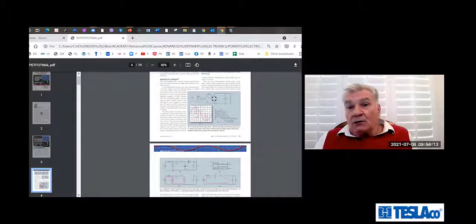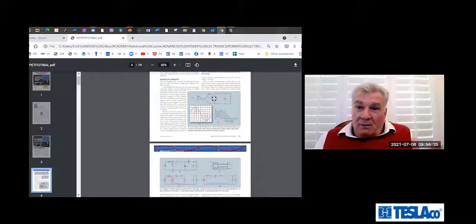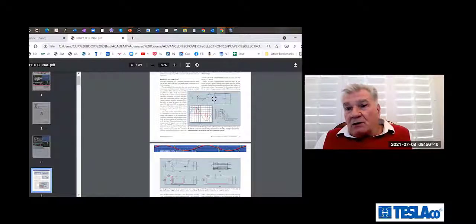Bad news: you're drawing current in pulses at the same frequency as the sine wave voltage on the input, but these pulses are high peak currents. Therefore, by Fourier series, these high peak currents have a tremendous number of harmonics. Since it's an odd function, it has only odd harmonics—first, third, fifth, and so on—but all harmonics are very high in magnitude.